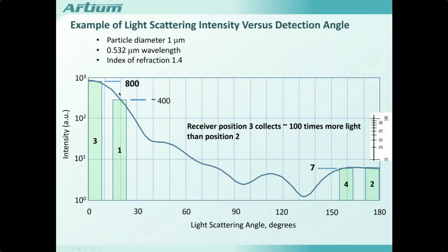So if we could get adequate signals with a 100 milliwatt laser with this scattering arrangement, we would need a 10 watt laser to get similar signals, and that's actually impractical. So there again, that's why I insist that, if possible, use an off-axis forward scatter detection configuration.